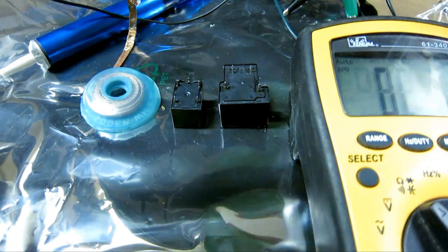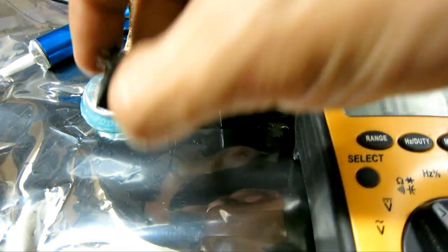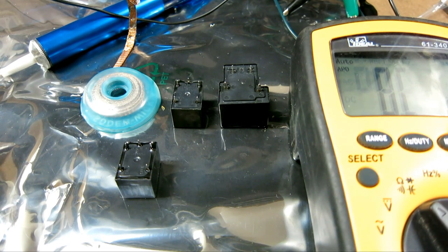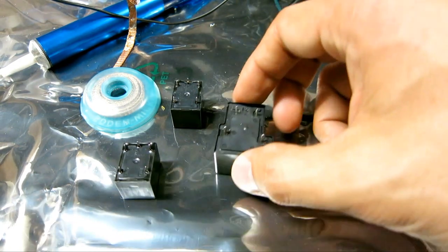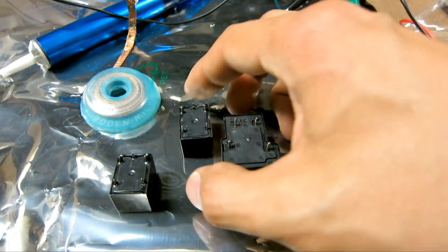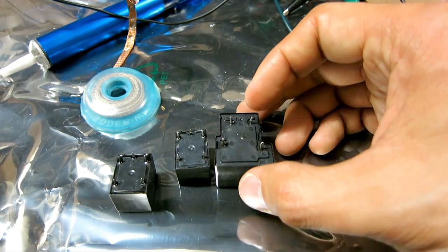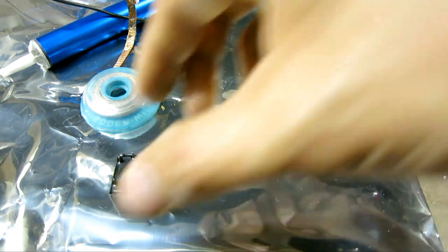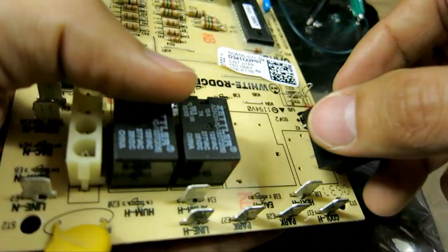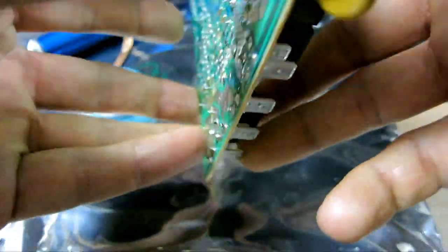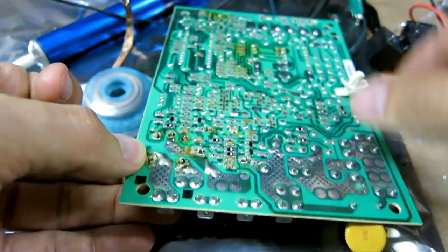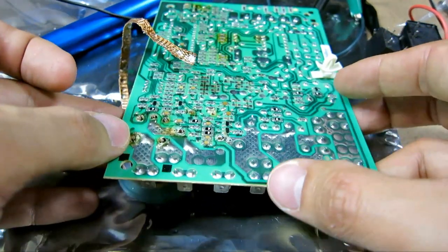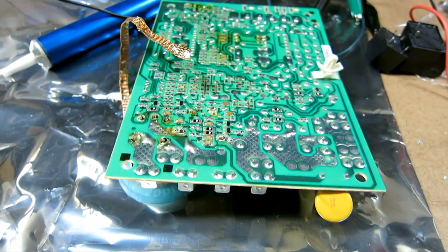But since I have two new relays to replace anyway, I'm going to go ahead and replace the relays and then reconnect the board, because sometimes these relays could be just intermitting. So I'm just going to go ahead and replace it with these new relays in here and then test it out. And if it still doesn't work, of course, we need to get a brand new board in. And we need to get a brand new board to begin with because this is just jerry rigging it and you're not supposed to do it like this anyway.